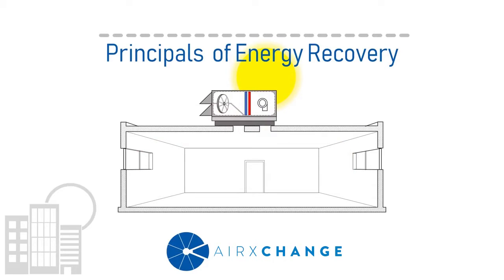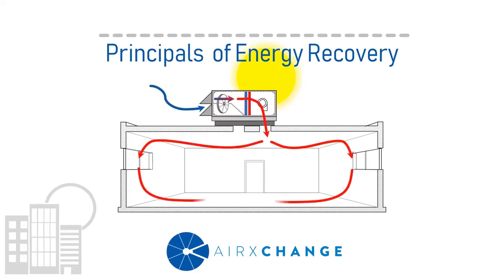Now let's look at that same process, but adding an energy recovery wheel to the system. Instead of the primary conditioning element having to treat the entire ventilation load, the energy in the exhausted air performs a large portion of the work, which significantly reduces the capacity required by the heating or the cooling element. I often refer to this process as a load shift, where you're shifting the air conditioning load over from a high-grade energy source to a low-grade energy source and still accomplishing the proper ventilation to the space.